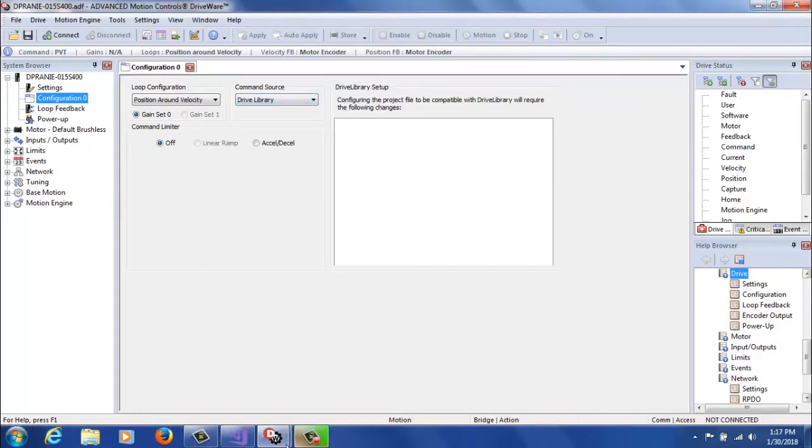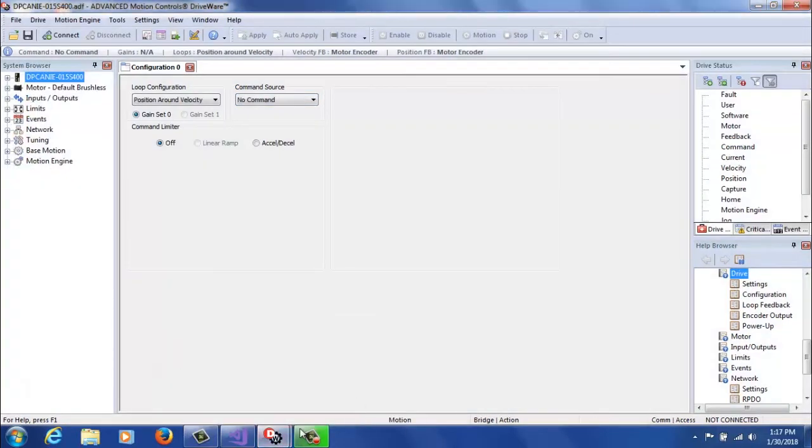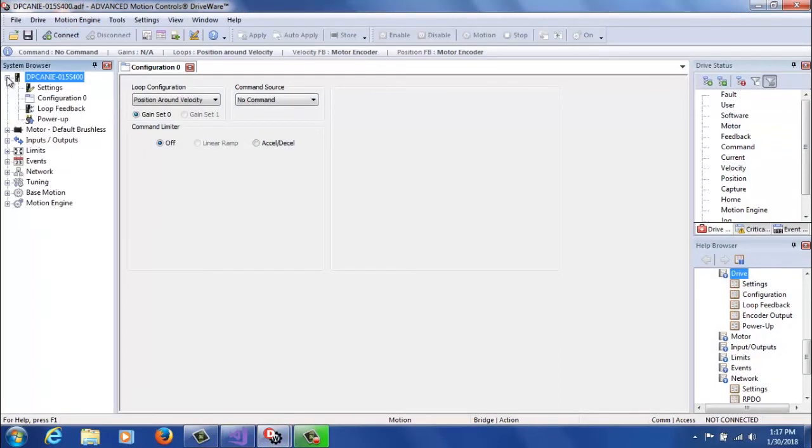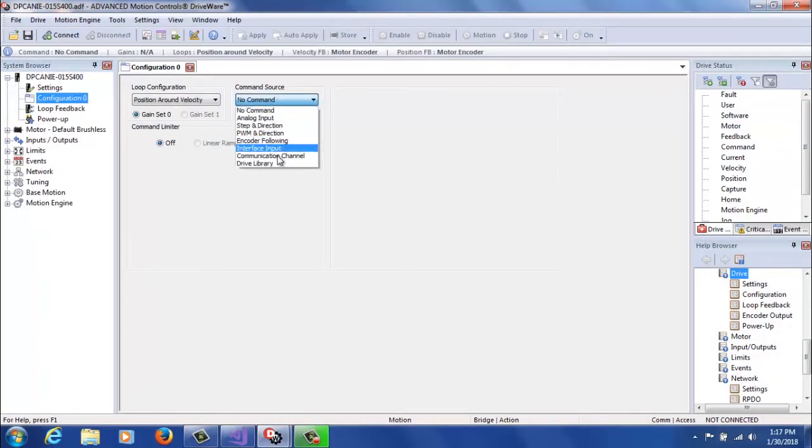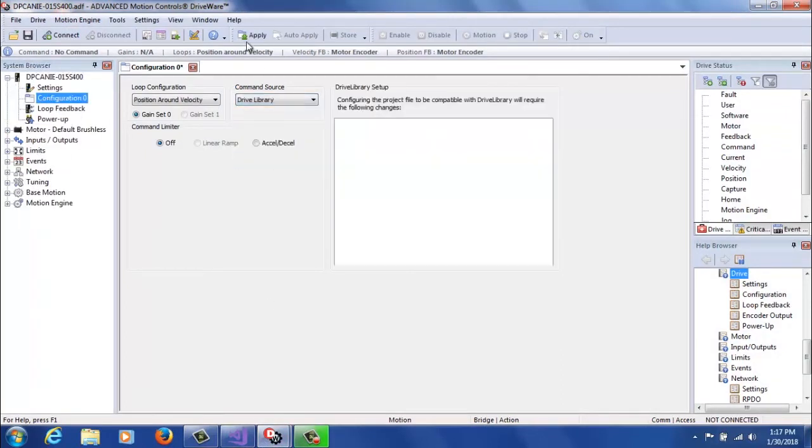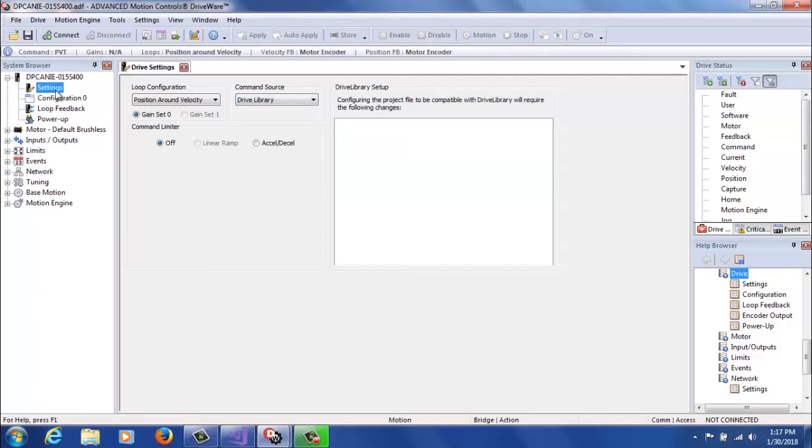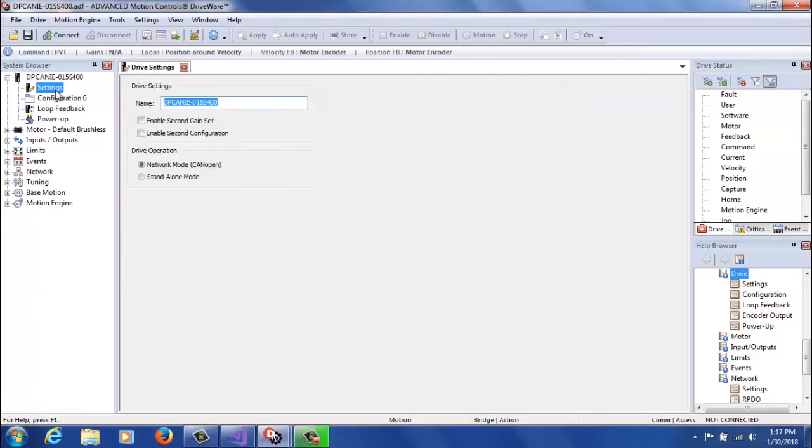For a CAN drive, you go through the same process. You start off going to configuration 0, setting the command source to drive library, but you're also going to go to settings and make sure it's set to network mode CANopen, so that it can receive commands over the CAN network.